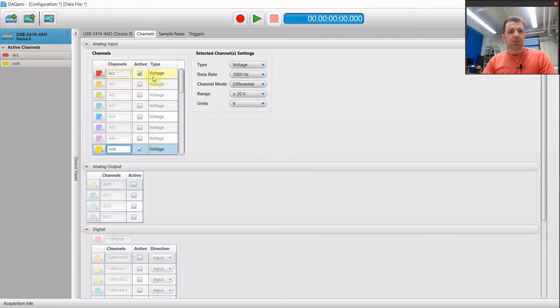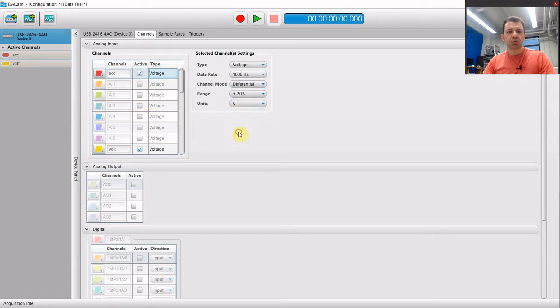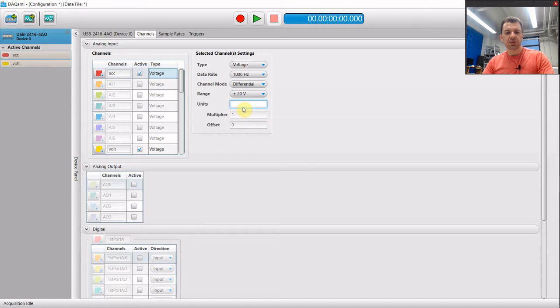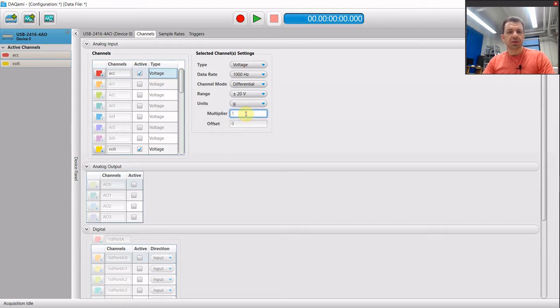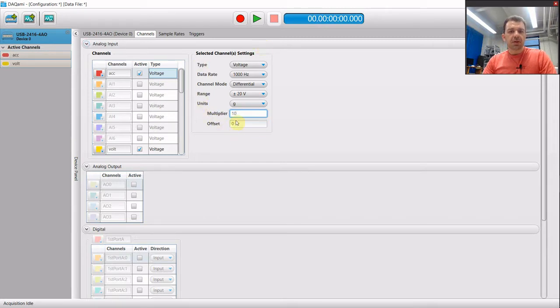Now for voltage we can accept voltage directly. For the acceleration we want to change the voltage reading to acceleration. So this is G, and this sensor has 10 G per volt scaling factor. This is it for the setup.